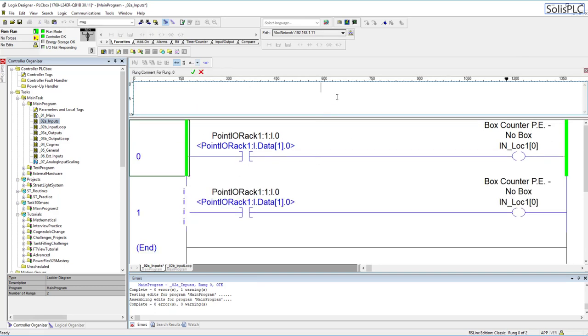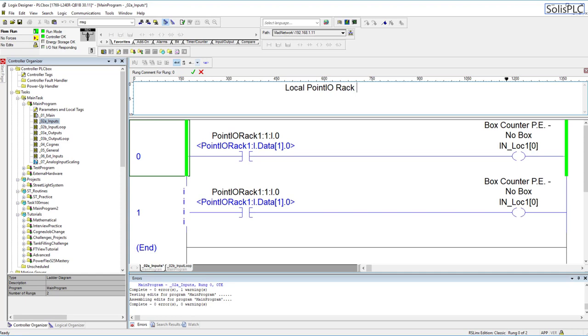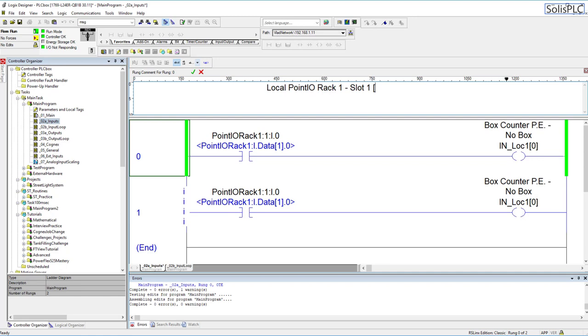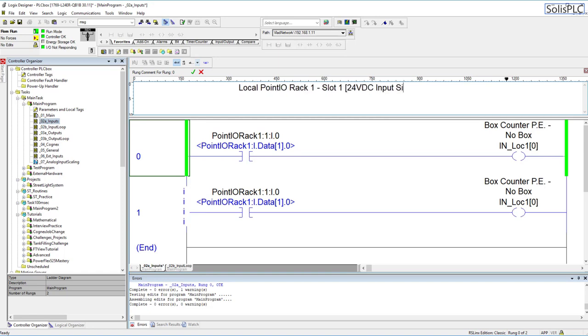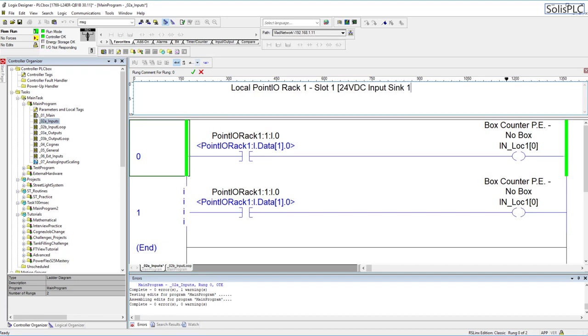I'm going to give the first rung a description of what the device or what the hardware is. This is going to be local point io rack one slot one. Here I usually put in a description so this is going to be 24VDC Input Sink and usually I give the card as well so this is going to be 1734 ib8.